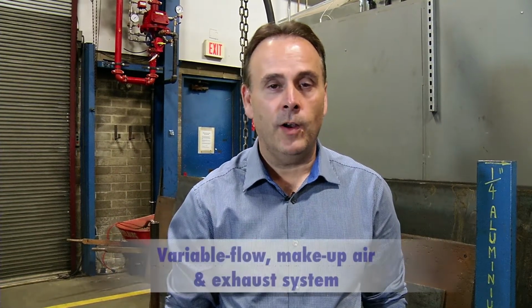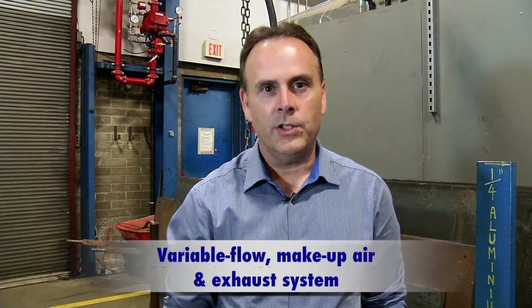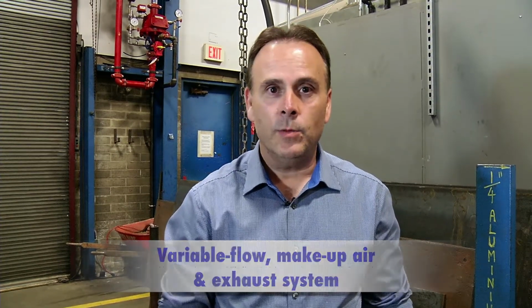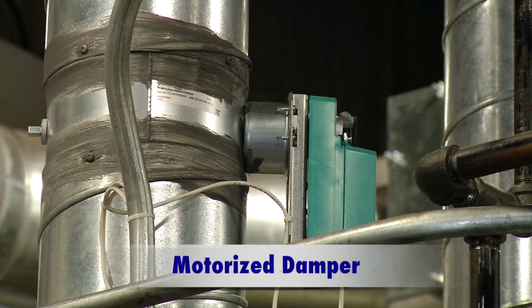So what we're going to look at today is the ventilation and exhaust system installed at BCIT, which is a variable flow makeup air and exhaust system. The way the exhaust system works is, as a student enters the booth, an occupancy sensor picks up their occupancy, and then a motorized damper, that blue device up there, essentially opens. And as each booth is occupied, each damper opens.